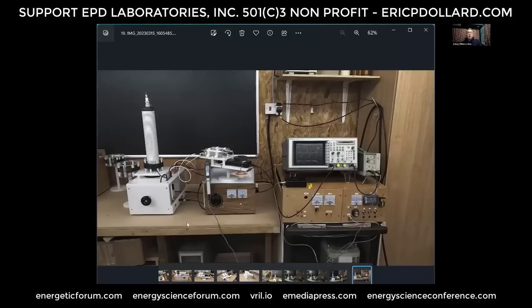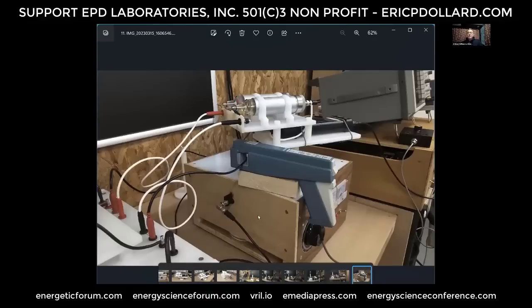Here in the middle of the picture, you can see a Tektronix current probe, a 50 amp current probe, which allows me to measure across the actual primary coil itself, both voltage and current profile, so we can see what that coil is being driven with, what the actual waveform is.